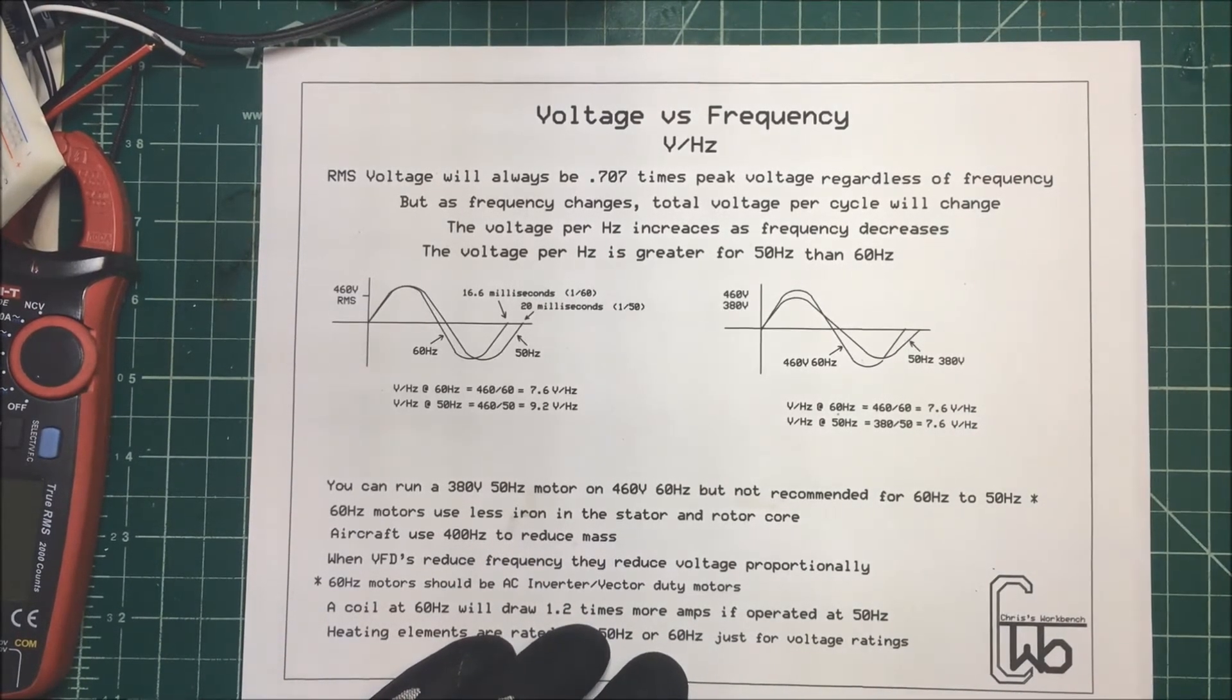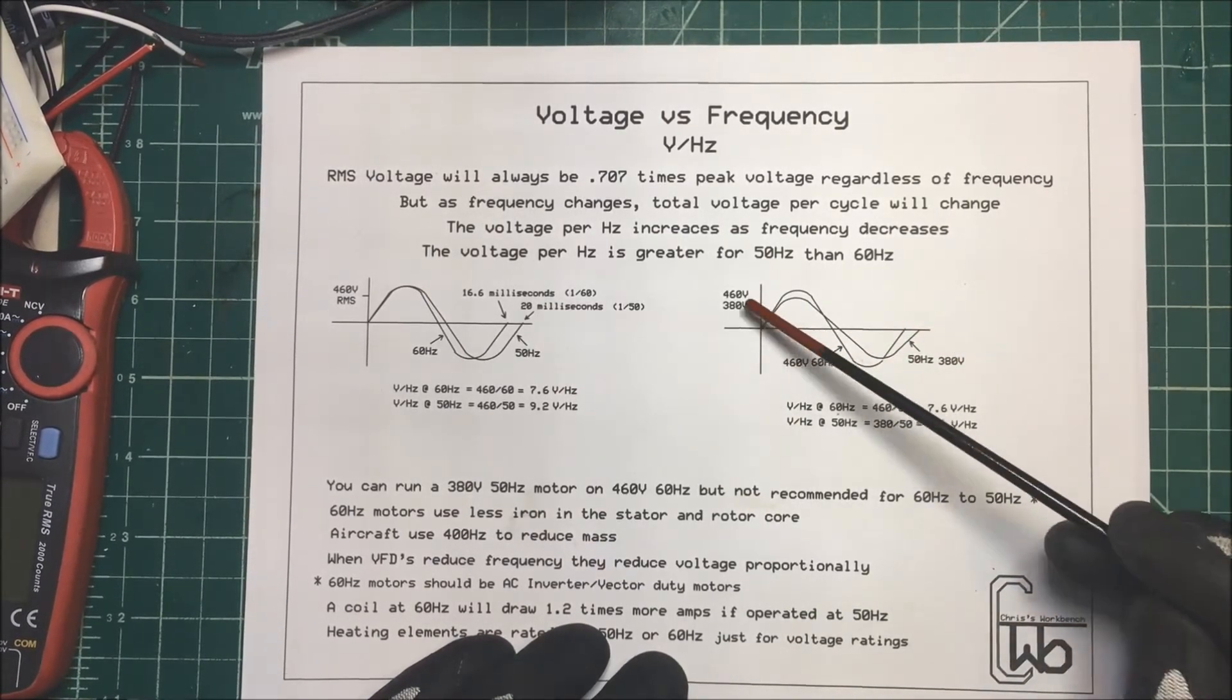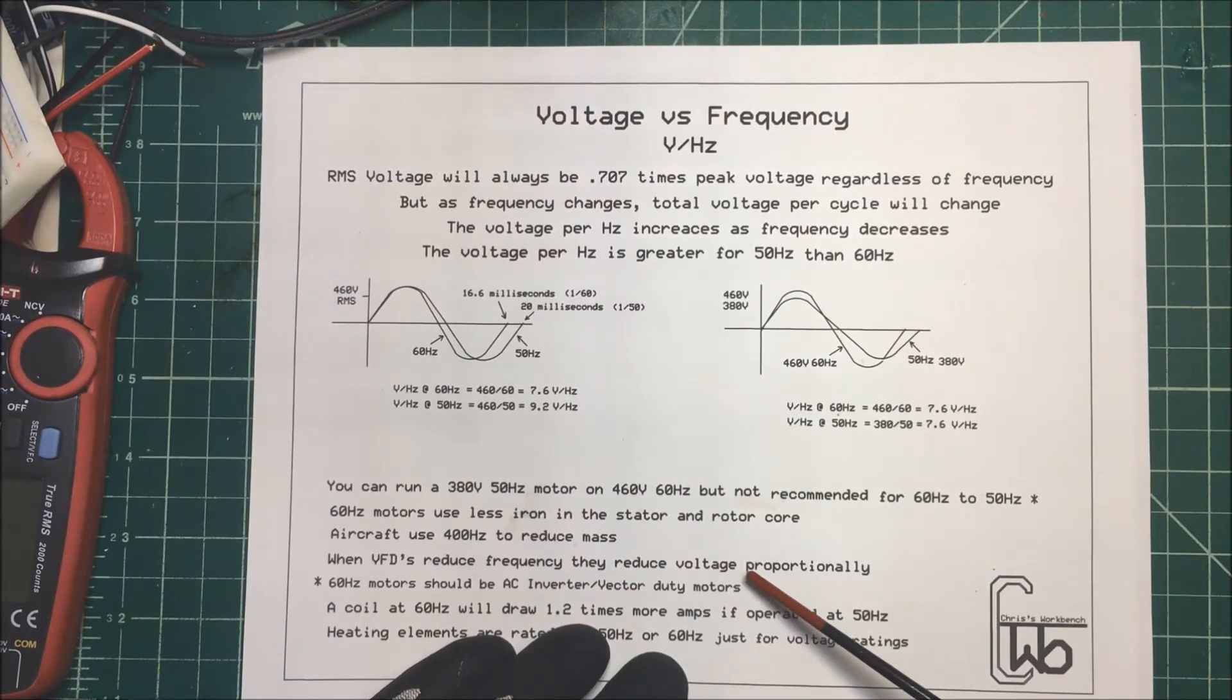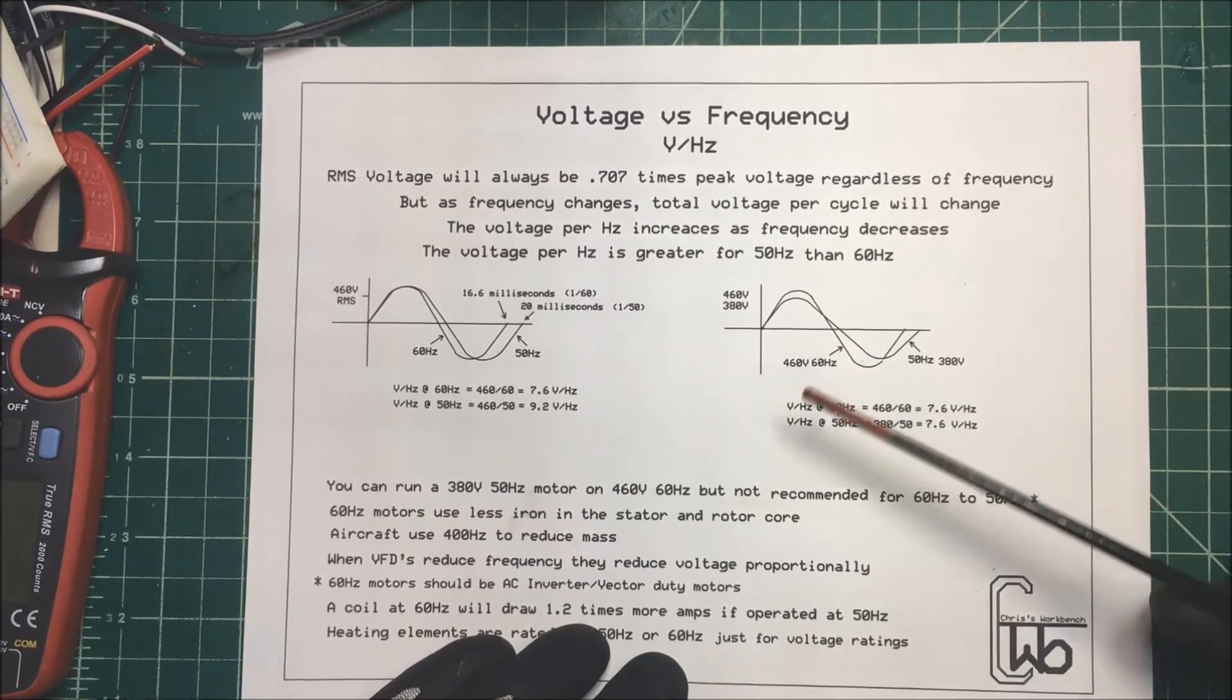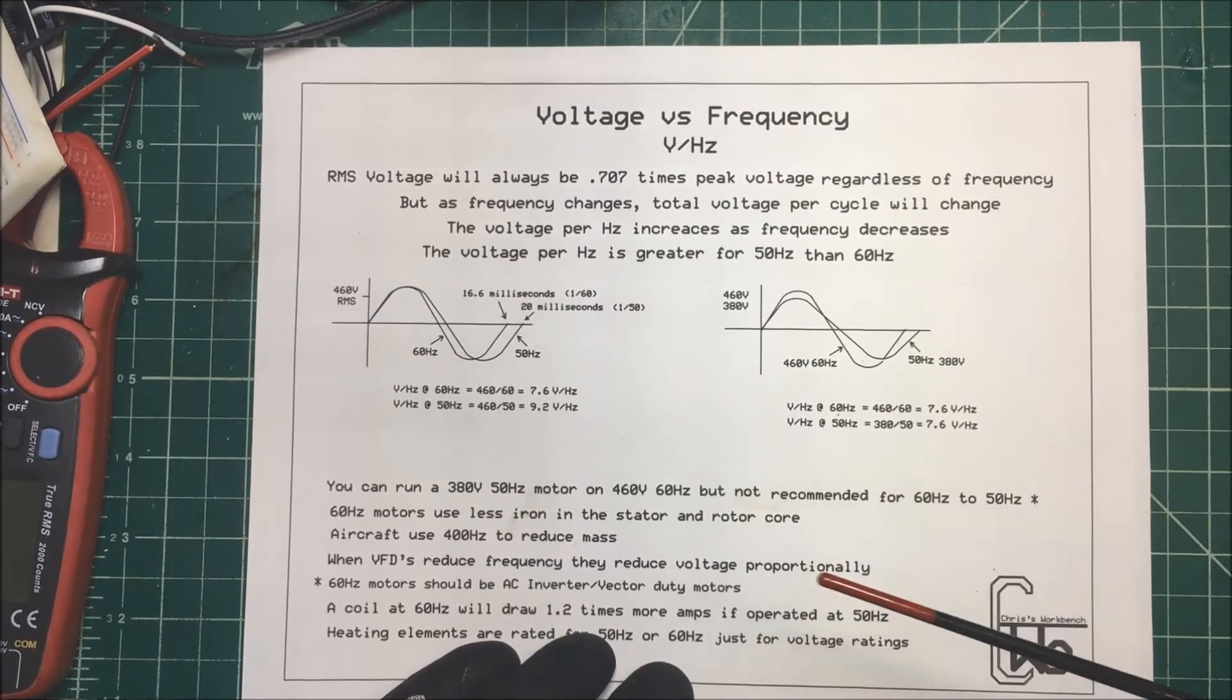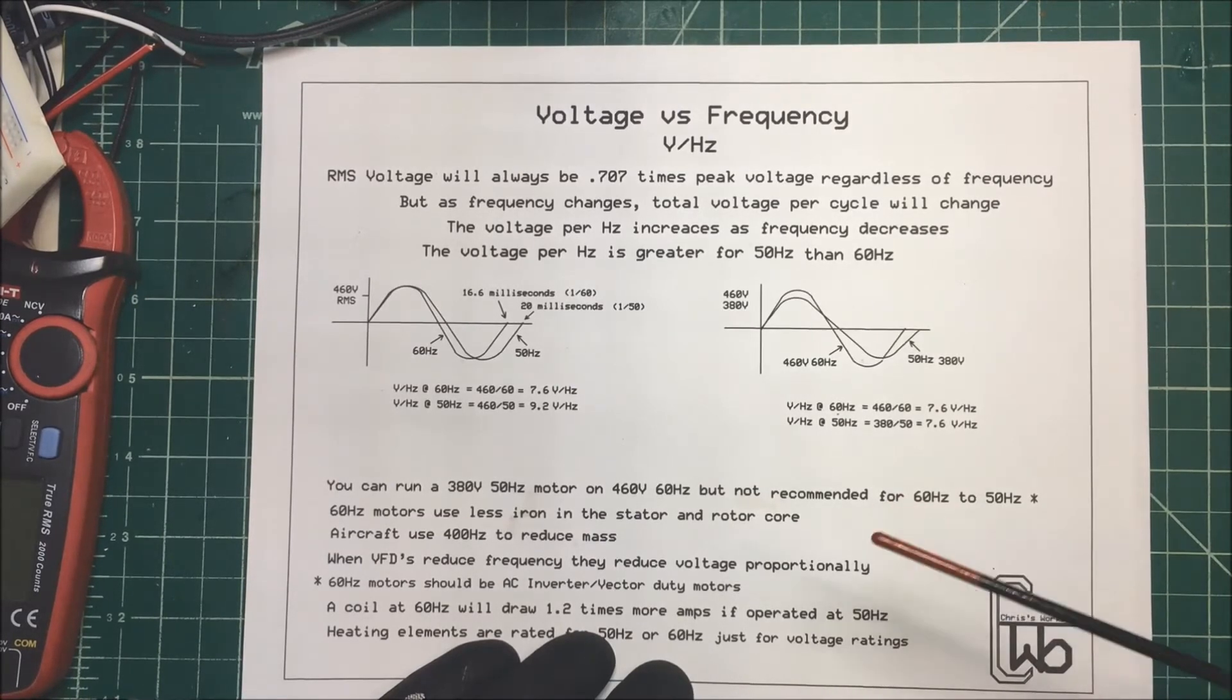But now we take and run a 460 volt motor at lower frequencies all the time. We use a VFD to reduce the frequency. And when we do that, it reduces the voltage proportionally. So at 50 hertz, it's going to give us 380 volts out of the VFD. But it's not recommended to run a standard 60 hertz motor that way because they can get hot.